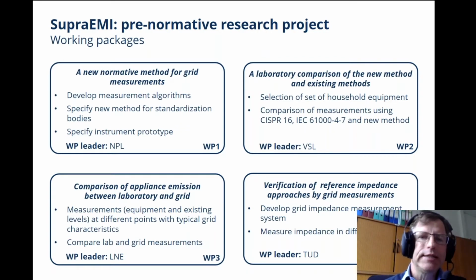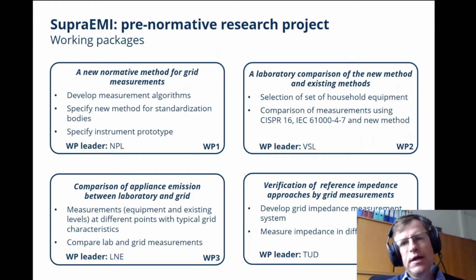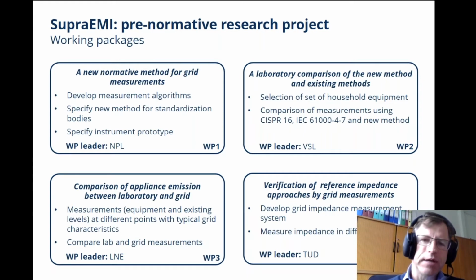And last but not least, we want to do a set of grid measurements with regard to the network harmonic impedance that is seen by the equipment in order to verify if that reference impedance that is used for emission testing is, let's say, realistic. So from that point of view, also for Angela, I think you can expect a few measurements of the network harmonic impedance up to the frequency of 150 kilohertz here.